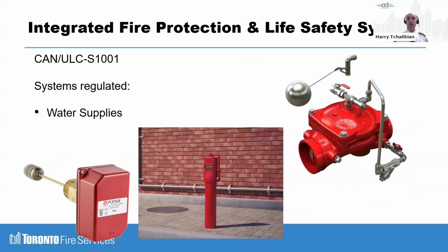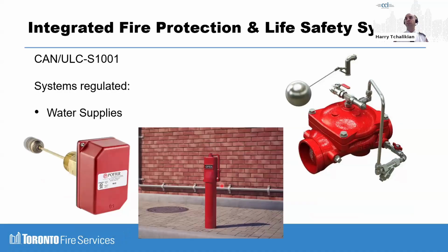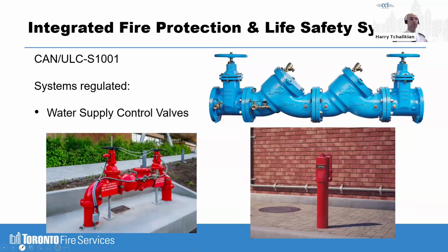Water supplies, any supervision, like what you see here is a post-indicating valve. Here's a float valve in a water tank, another float valve. Just make sure that they're working properly and reporting to the fire alarm system. Water supplies is addressed separately, exact same requirements.